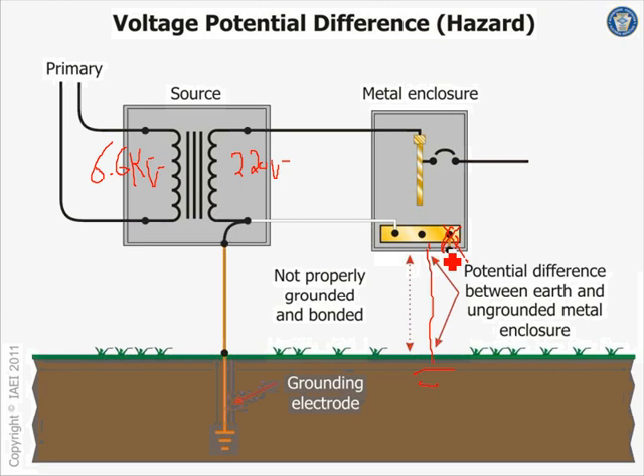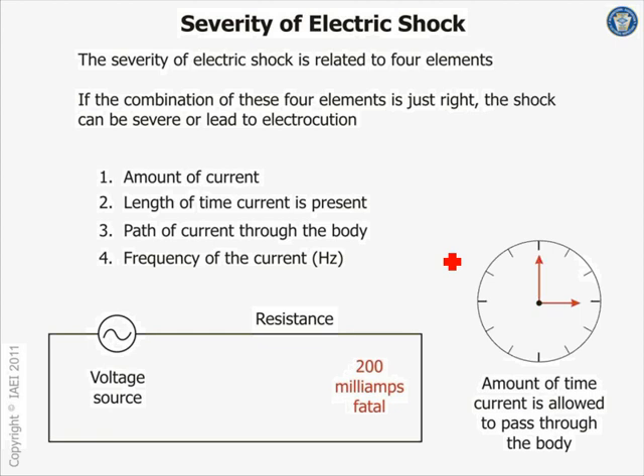So they say the voltage potential difference here will be high. I dare to say, being an engineer, at that voltage, not a whole lot of high voltage. If you're doing higher than 600 volts, that becomes very high. But typically, from your neutral to your building, we talk about a typical building, what, 100 feet maybe, maximum 200 feet maybe, 300 feet if it's a bigger building, from this transformer to where the panel is. So at that level, the difference should not be that substantial. But based on the code, your system is grounded. You must create a grounding electrode system here and bond it to the neutral. So this talks about the shock hazard.